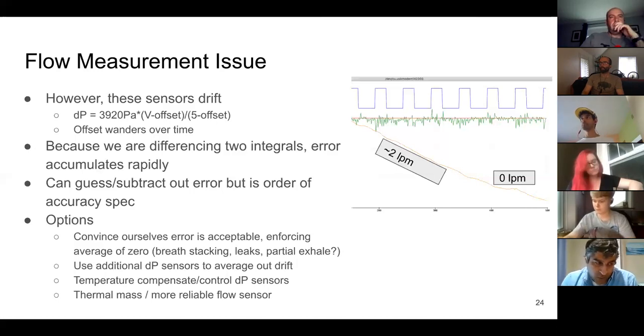What I've seen in a lot of older ventilators is an auto-zeroing valve where they pneumatically short the two inputs together periodically and measure the offset. That happens either every breath or every couple of minutes. Electrically or pneumatically? Pneumatically. Oh, every breath. I would really love to learn more about that. If we did it every breath, that would be something. Yeah, we could potentially do that. Well, let's think about that.